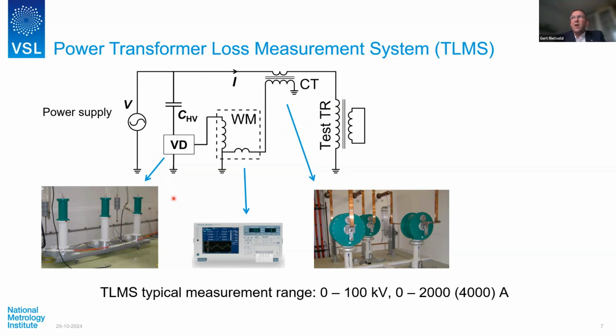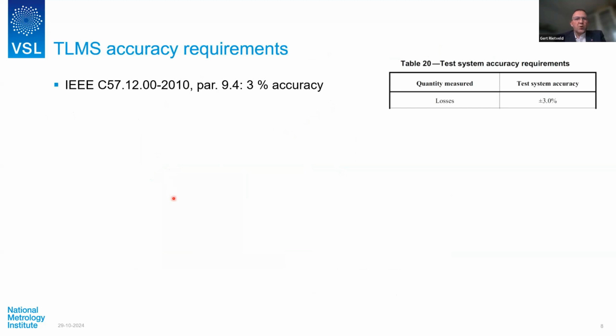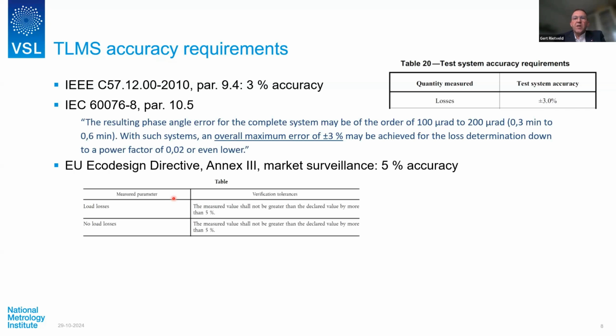Well, when it comes to reliability, there is, of course, a requirement on how accurate this measurement should be. And the key requirement comes from this IEEE standard that really requires 3% accuracy in the loss measurement down to a power factor of 0.01. And there are similar statements in the IEC standard. An overall maximum error of 3% may be achieved.